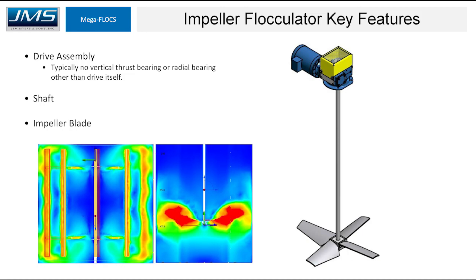Moving on to the impeller flocculator — again, the shaft is directly inserted into the gearbox, so all thrust and radial forces are experienced by that gearbox. The tip speed typically violates Ten State Standards of 3 feet per second, usually running in the 6 to 9 feet per second range, meaning floc particles are sheared at the blades. These rely on the pumping action of the water to create flocculation, and the output is generally a low-quality pin floc. A CFD analysis shows high shear areas at the impeller versus the paddle wheel.